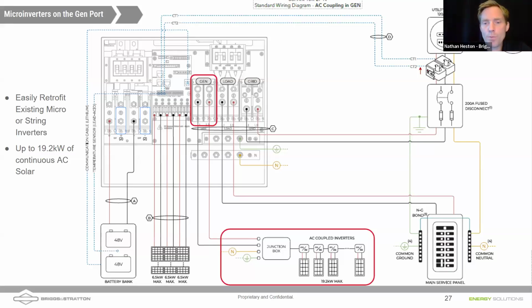Daniel, we're looking here at bringing that AC coupled array. This is the single line diagram or multi-line diagram coming from the Sol-Ark manual itself. And we're showing bringing those AC coupled inverters in through the generator port of a Sol-Ark. It's worth keeping in mind here that if we also want to tie a generator in, we don't have the generator port available now. So we're going to talk to you later about the ability to still use AC coupled solar and a generator at the same time.